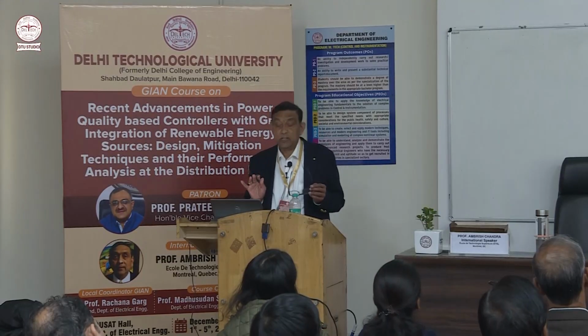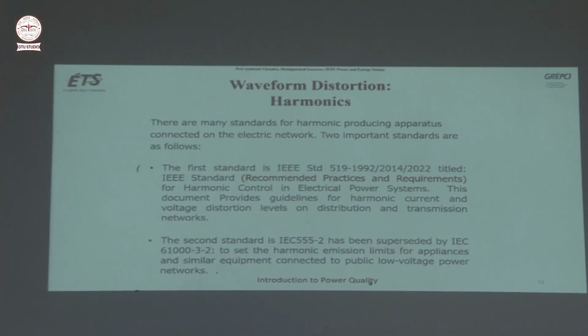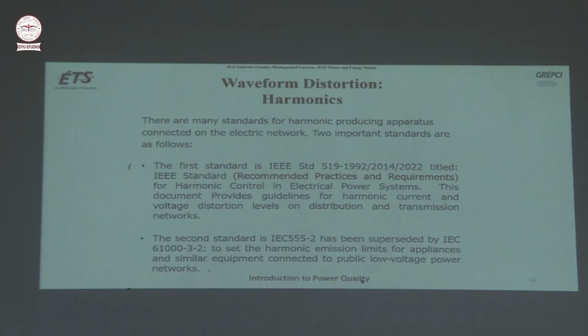There are many standards for harmonic producing apparatus connected on the electric network. Two important standards, IEEE standard 519, which was originally introduced in 1992 and it was a very popular standard, and that standard is still going on. What they have done, they have done some minor adjustment in 2014, and then in 2022 also they did minor ones. But most of the things still remain, the harmonic limits and those things, they still remain the same.